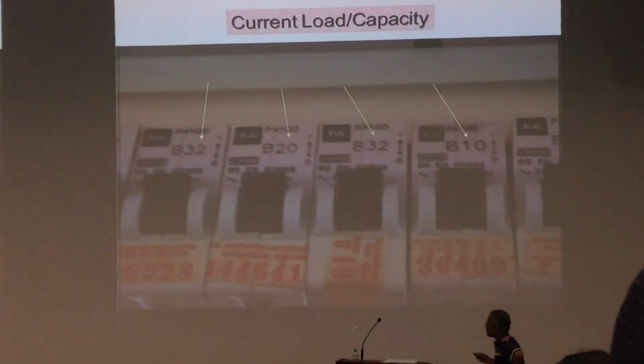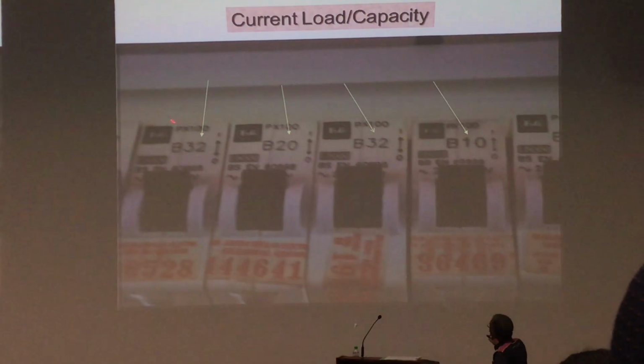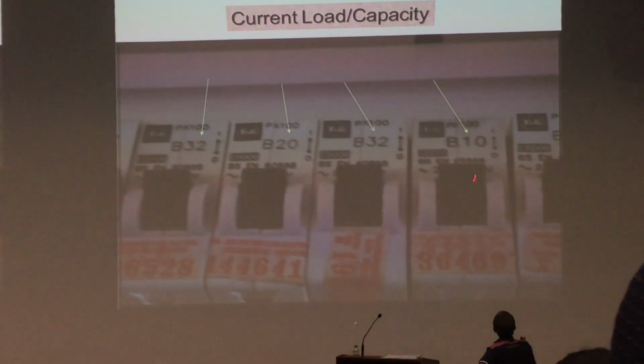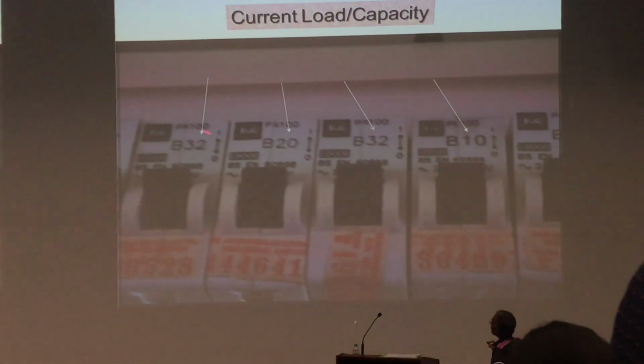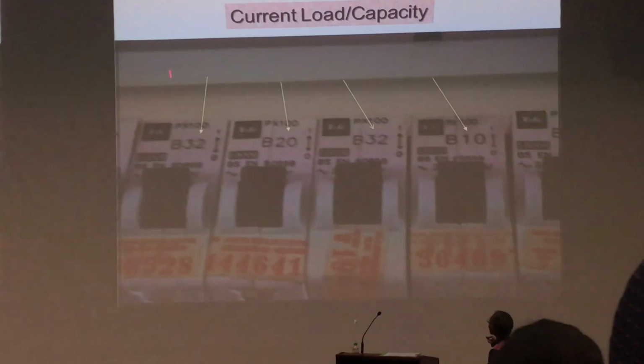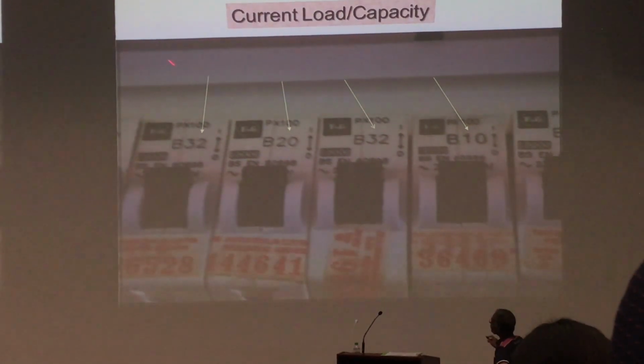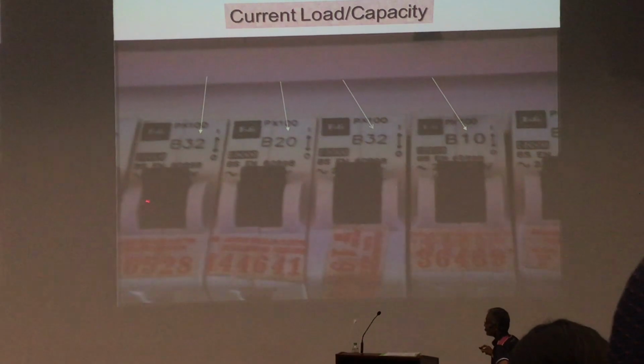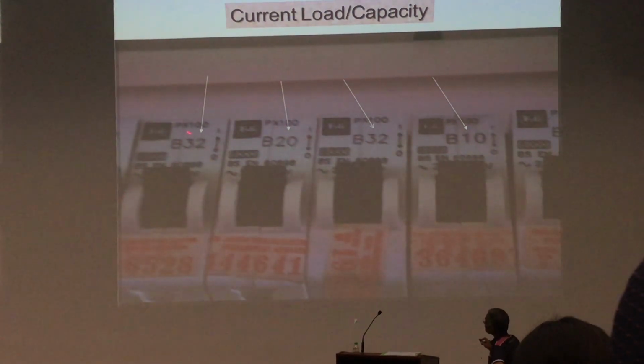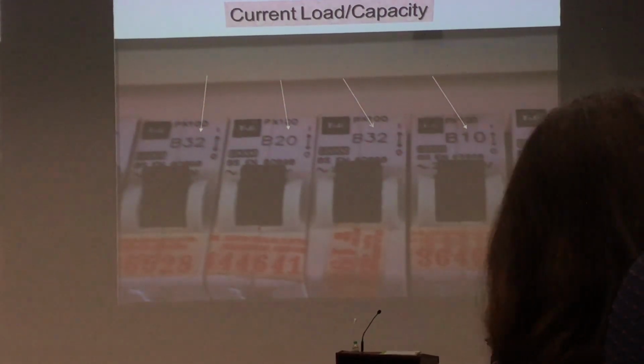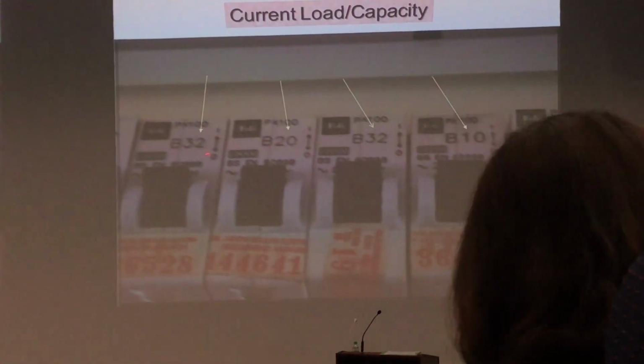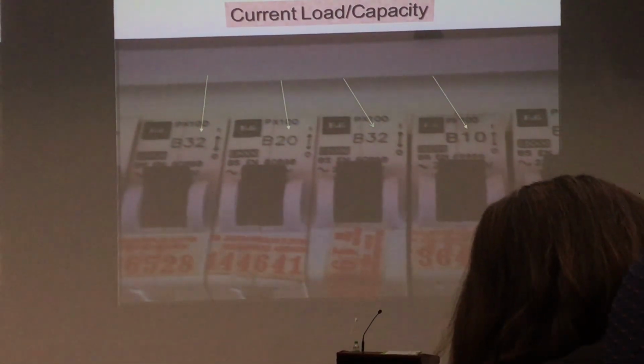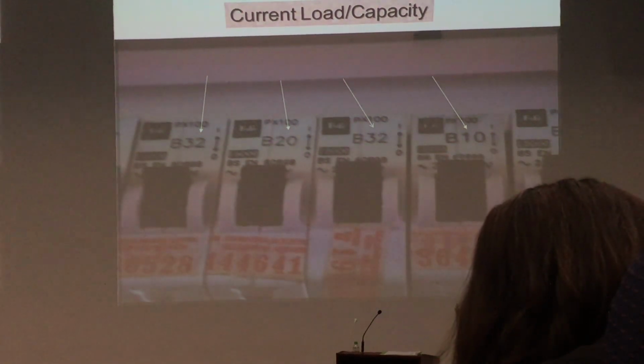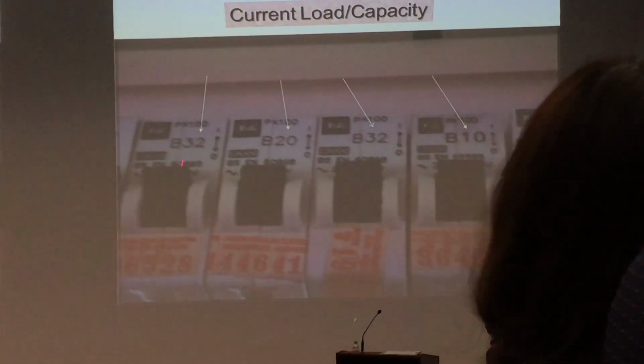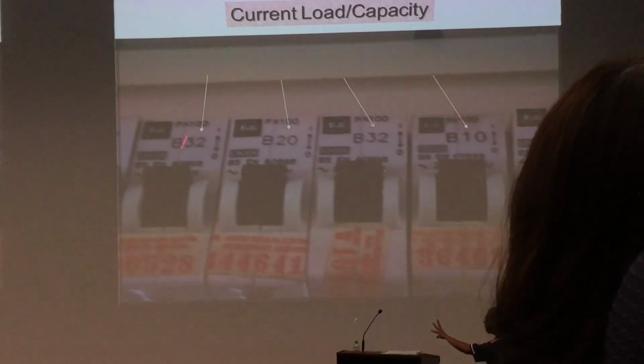For example, over here one cable. So 1, 2, 3, 4, 6 cables for example. This cable can stand up to 32 amp. Let's say the current going through here is 50. This will get disconnected, because the maximum current that can go through this fuse is 32. Now the current flow is 40, for example, you get disconnected. Trip, like that. Understand? So blackout to the sockets supplied by this fuse.